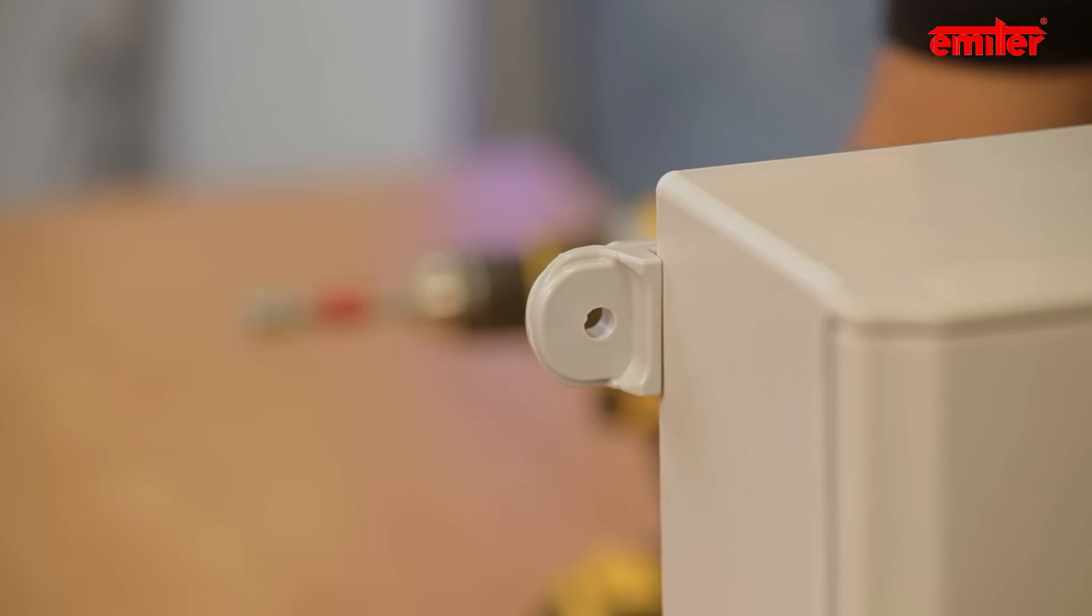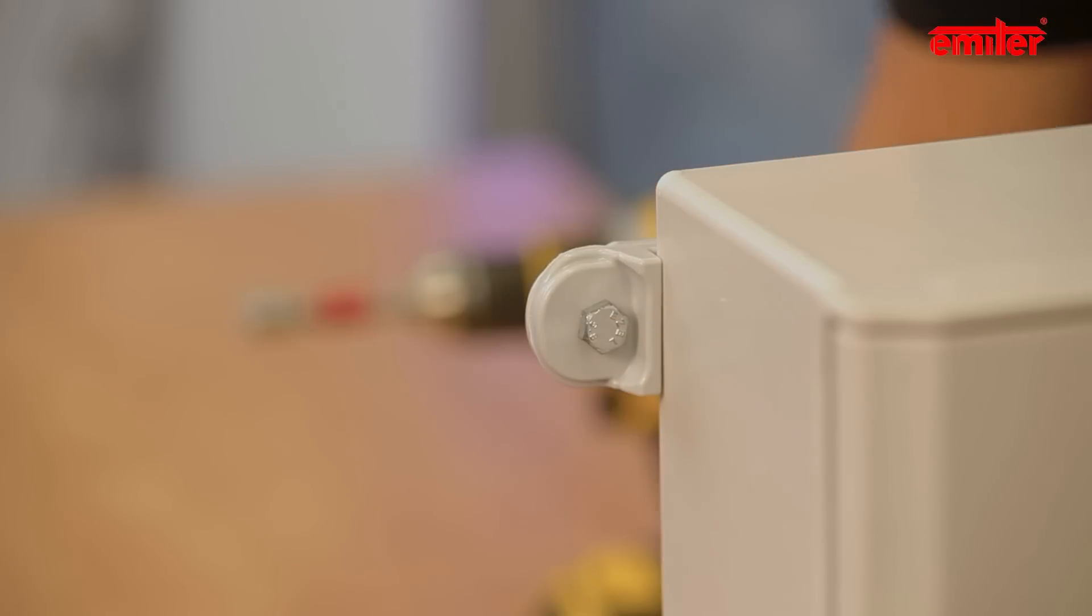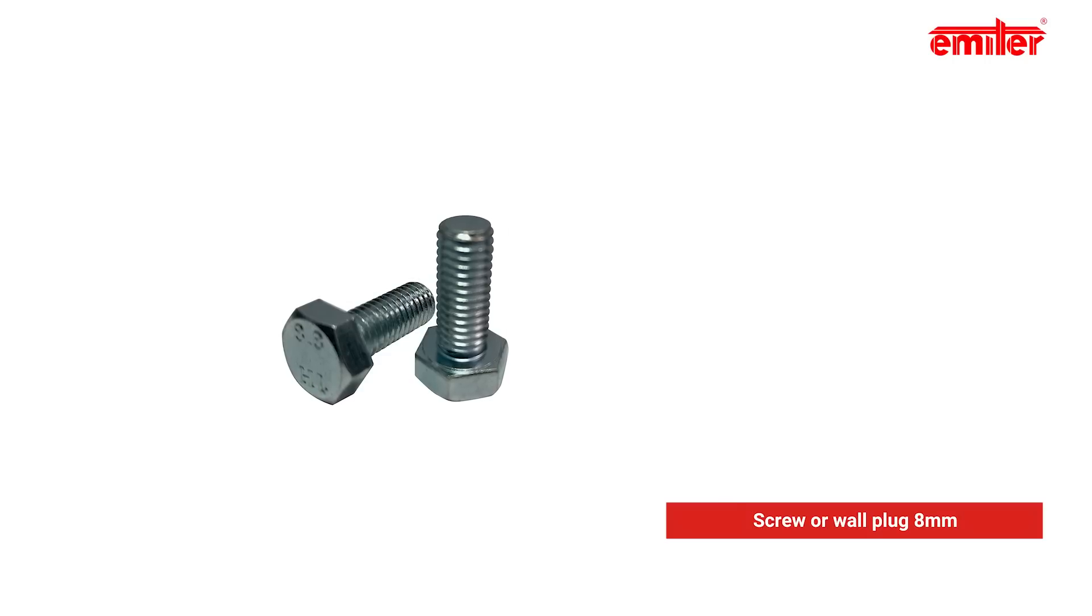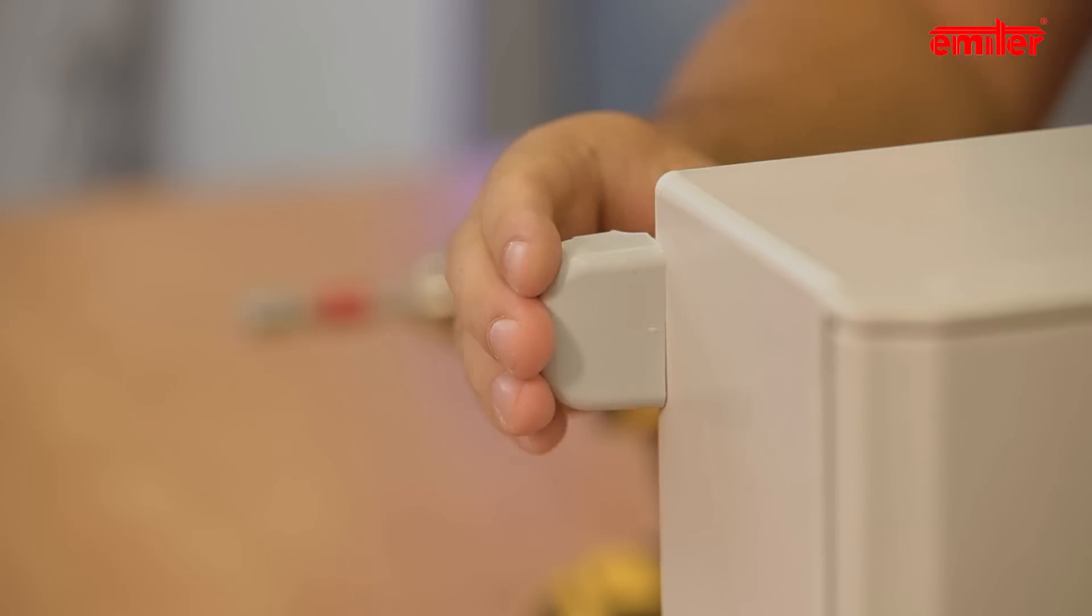Holders are installed. Now we need to remove the plugs and assemble it to the wall or frame construction. The hole in the UMWK holder allows to use screws or wall plugs with a diameter of 8 mm. After enclosure installation, cover the visible part of the holders with the plug.